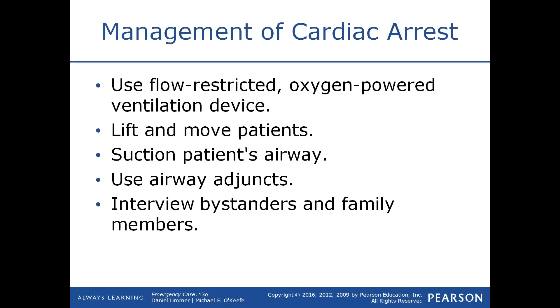There are semi-automatic AEDs and there are fully automatic AEDs. Fully automated AEDs are something that you might see in an area where they rarely ever use an AED. It does not advise the EMT to take any action at all. What you do is you open the lid. When you open the lid, it automatically turns on. It automatically starts talking to you and tells you to put the patches on the chest. And once you put the patches on the chest, there's no more pushing any other buttons. There's no more charge, shock. The machine automatically identifies the rhythm, the machine automatically charges, and the machine automatically defibrillates.